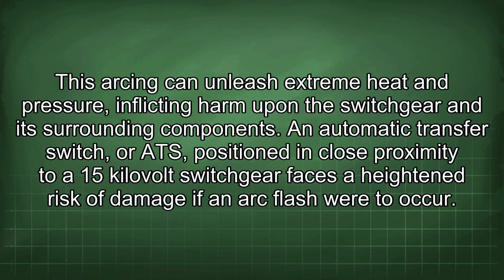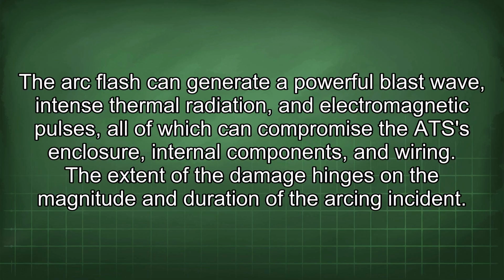This arcing can unleash extreme heat and pressure, inflicting harm upon the switchgear and its surrounding components. An automatic transfer switch, or ATS, positioned in close proximity to a 15 kilovolt switchgear faces a heightened risk of damage if an arc flash were to occur. The arc flash can generate a powerful blast wave, intense thermal radiation, and electromagnetic pulses, all of which can compromise the ATS enclosure, internal components, and wiring. The extent of the damage hinges on the magnitude and duration of the arcing incident.